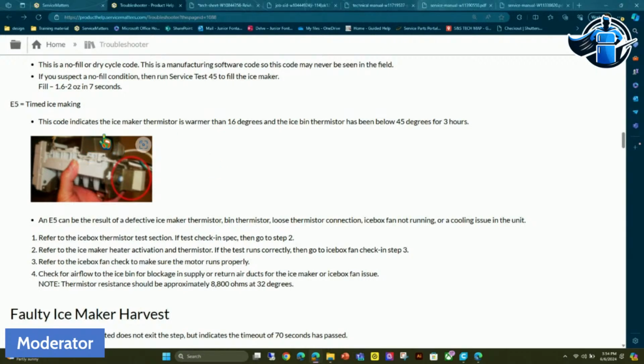This code indicates the ice maker thermistor is warmer than 16 degrees and the ice bin thermistor has been below 45 degrees for 3 hours. Again, there's a temperature issue. The unit's pretty much going to go into a lockout if those temperatures are monitored. We're looking for 11 degrees, so anything over 11 degrees, we're really going to go into a timed ice making, where this ice maker might only eject ice every 8 hours or so.